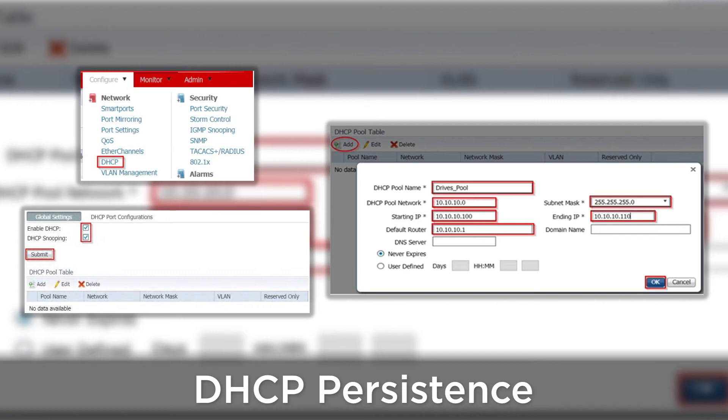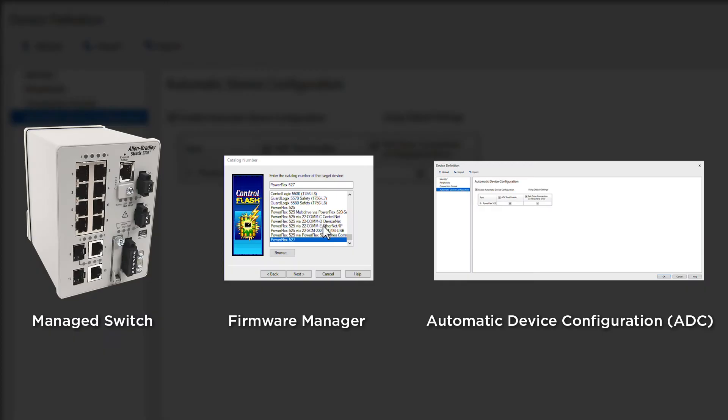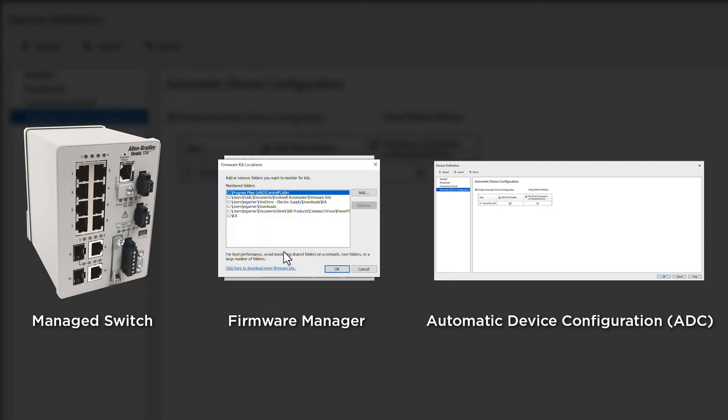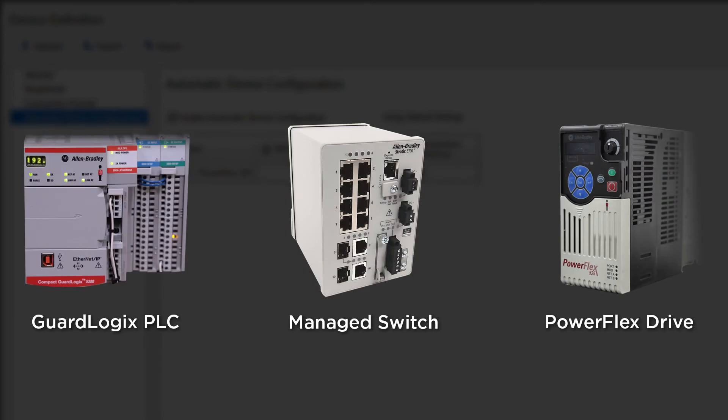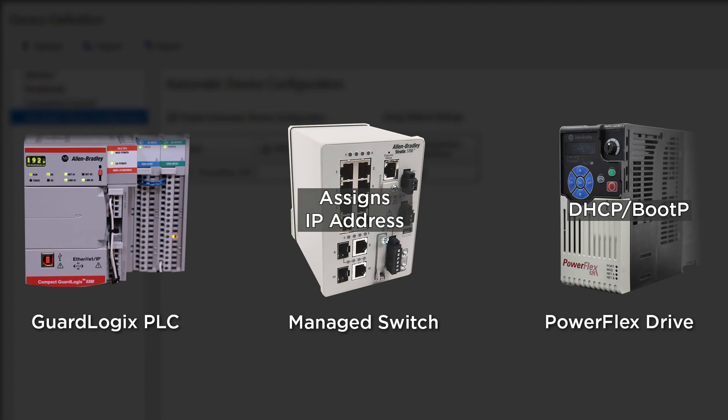DHCP persistence allows you to assign a specific IP address based on each port of the managed switch. With a managed switch, firmware manager, and ADC, you will be able to unplug a failed drive, install a new one, and be back up and running in a matter of minutes. Out of the box, the PowerFlex drives are set up for DHCP slash boot P, so the switch will assign the address.